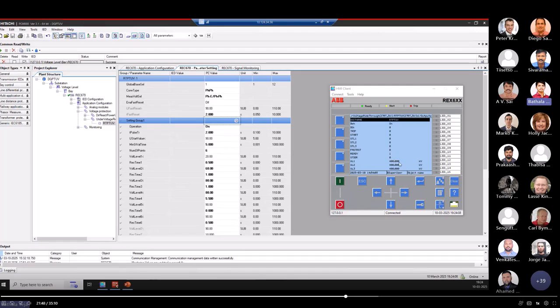After ready, once ready is high, the function starts looking for under voltage condition. Here the initial U start level is given as 90%. So I apply 85%, which is basically an under voltage condition. In the first example, I am keeping 85% continuously. I applied 85% of voltage in UL1. You can see start immediately, but trip you will see only after some time. Like it's still zero. It is one now and it is resetting.